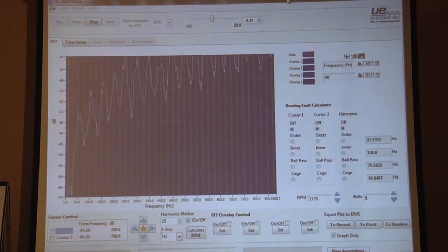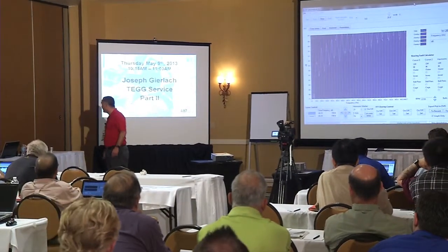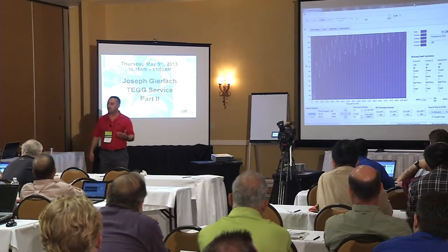That sounds similar, doesn't it? Slightly different frequency spectrum, but looking at the 25 hertz way down here, does everybody see that? At the very bottom, but it's still hitting on 25 hertz. Unless you've got an explanation, I don't know why that would be down below. But it's there, isn't it? It's a 25 hertz harmonic.